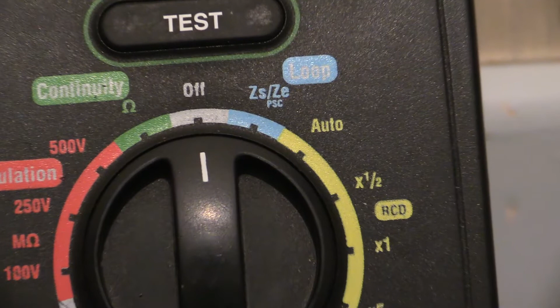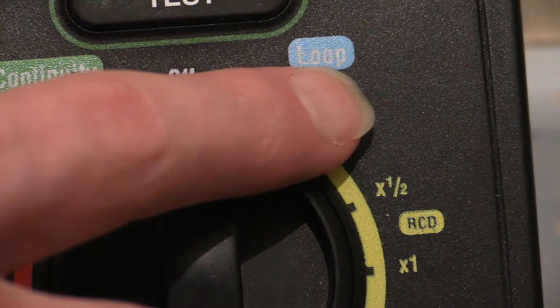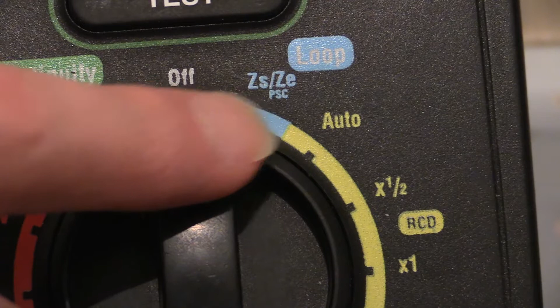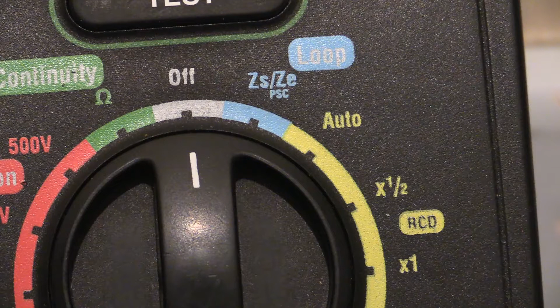What that is for is carrying out tests associated with the electricity supply characteristics. As you can see there, it says ZS and ZE, and prospective short circuit currents, and all that lot. One test you'll do will be live to neutral, and the other test you'll do will be live to earth, and you'll get two different test results, and they should be within a certain tolerance.